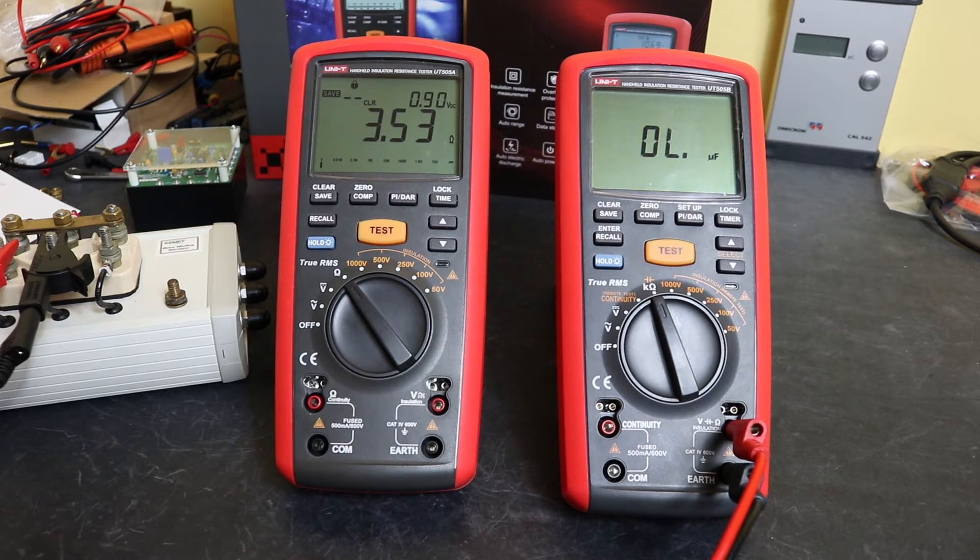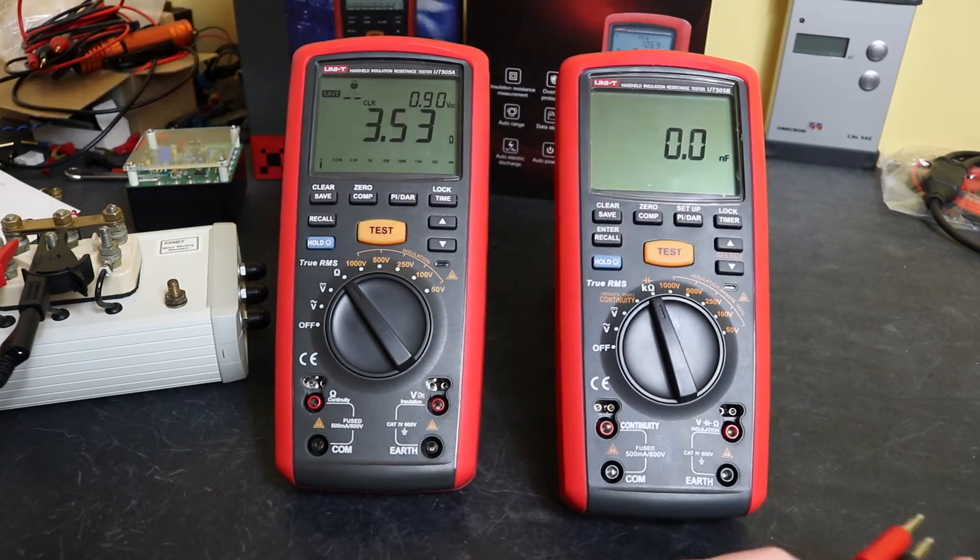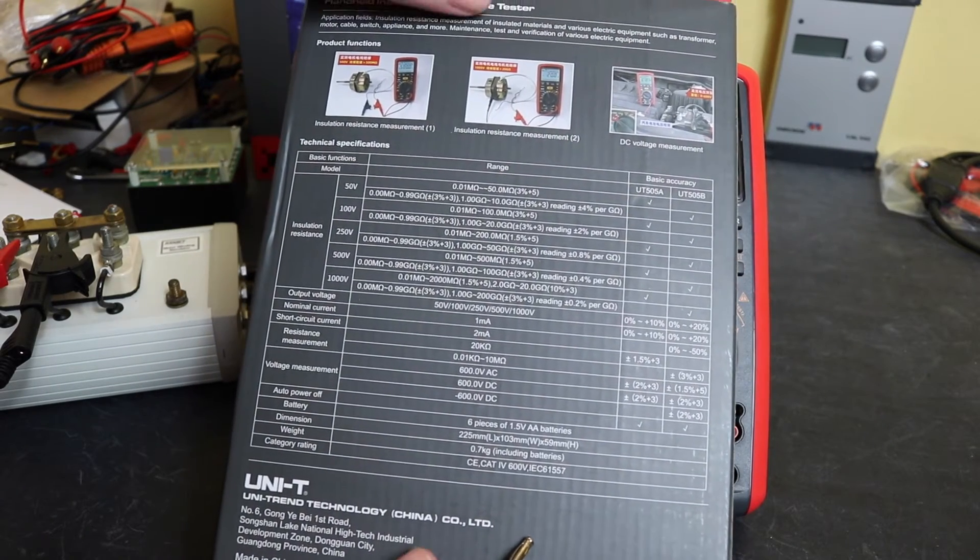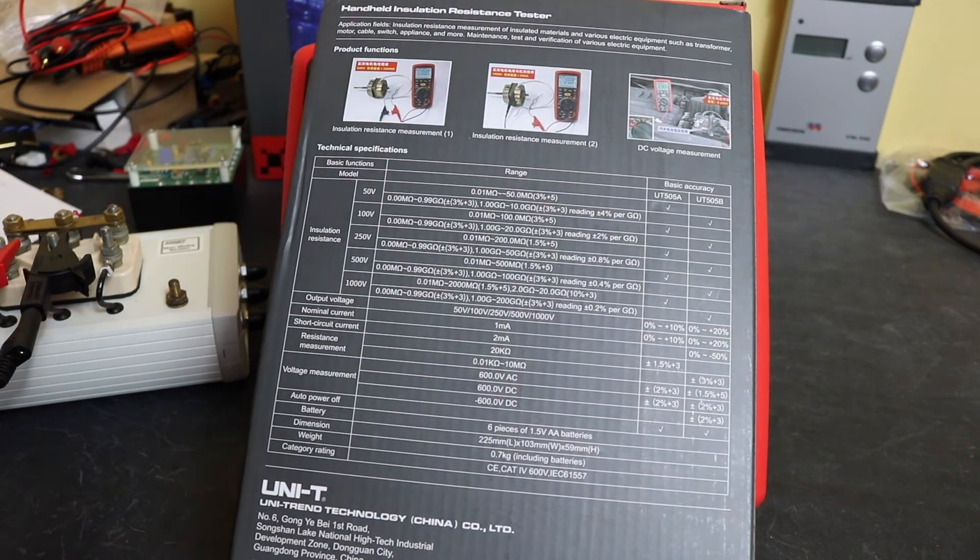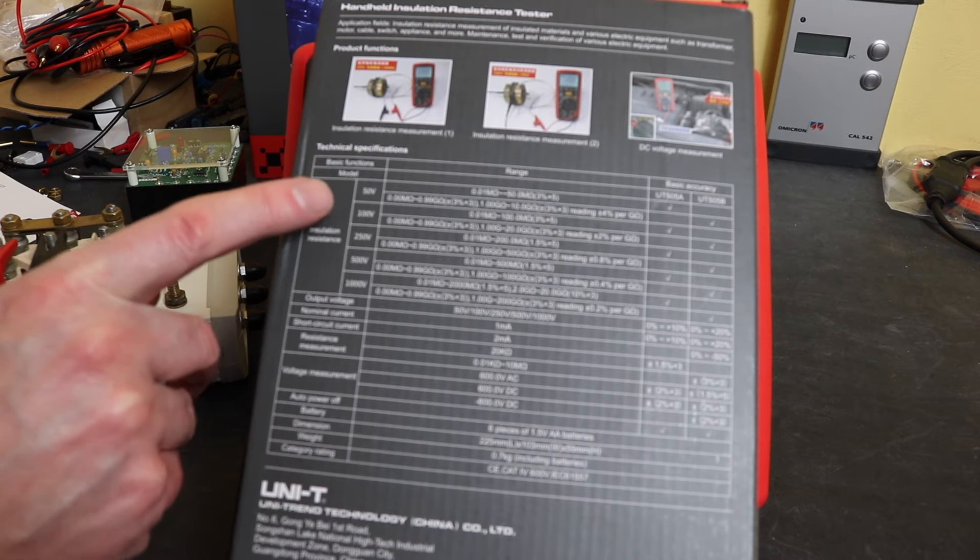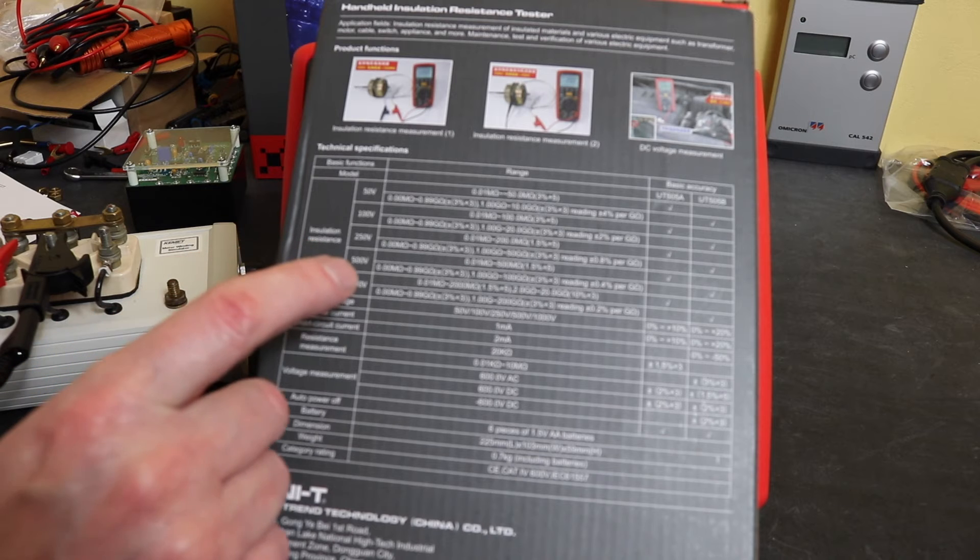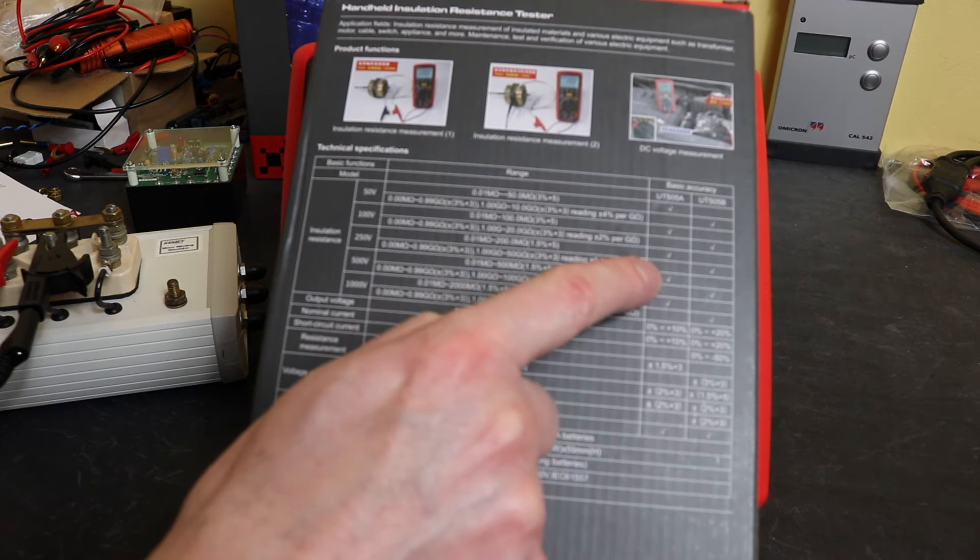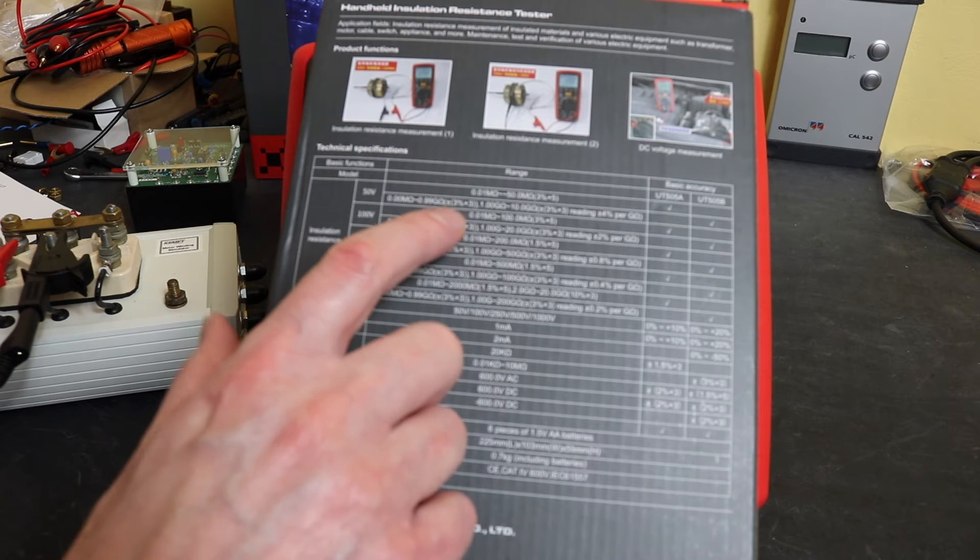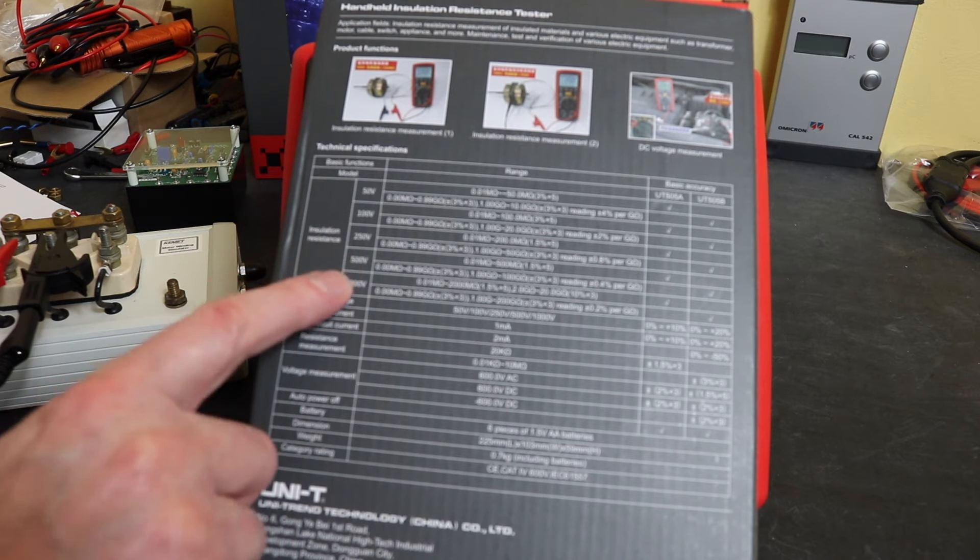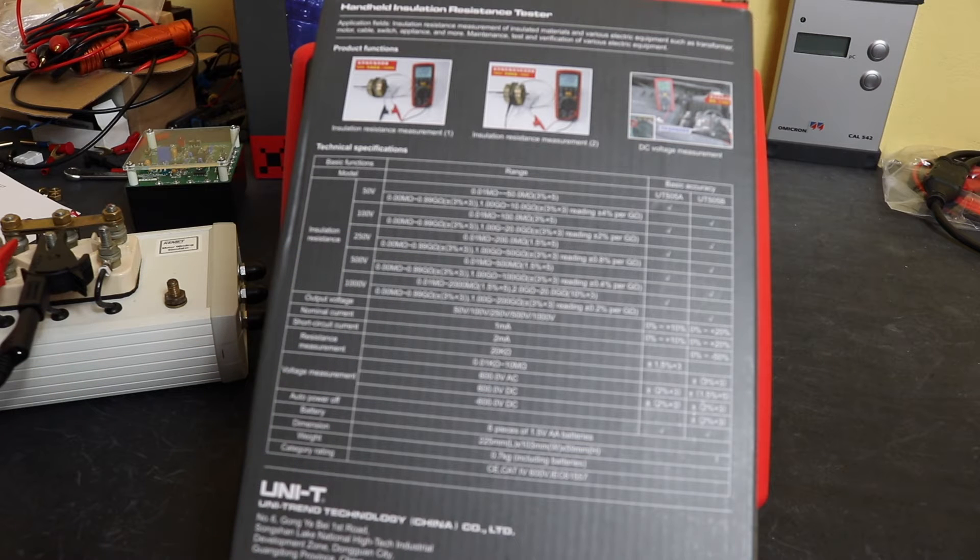You then move on to the insulation test functions. What you can actually do on the box that came with the UT505B, you do actually get a little table on the back that shows you what the difference is between the two instruments, especially with regard to the insulation test function. You can actually see they all have the same voltage. However, on the UT505B you get these extended ranges that you don't see on the UT505A. Accuracy wise, you get a slightly better response from the UT505B for the lower settings. However, as you get up to the higher voltages, that switches and you get a slightly better accuracy specification for the UT505A.